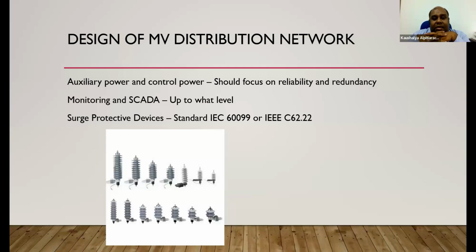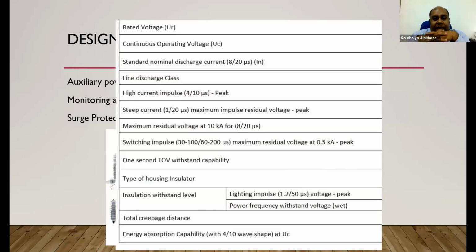Monitoring and SCADA up to the level that you need. Surge protective devices. This has nothing to do with 62305. Your standard is 60099, or you can go with IEEE C62.22. These are some specification jargon that you need to accomplish and finalize before ordering or before completing the design.